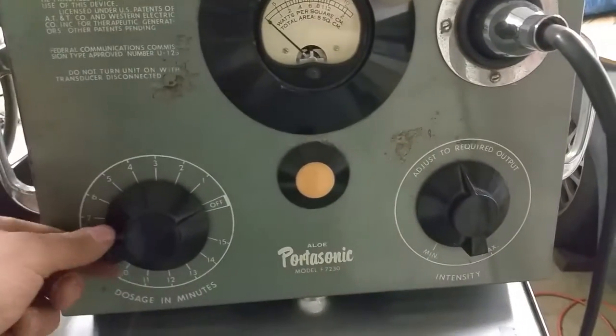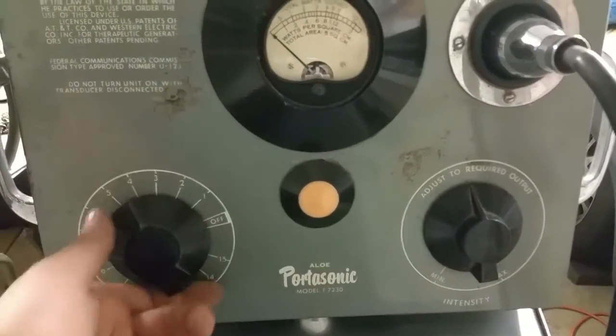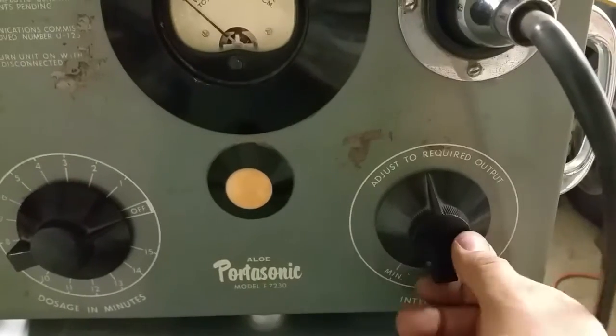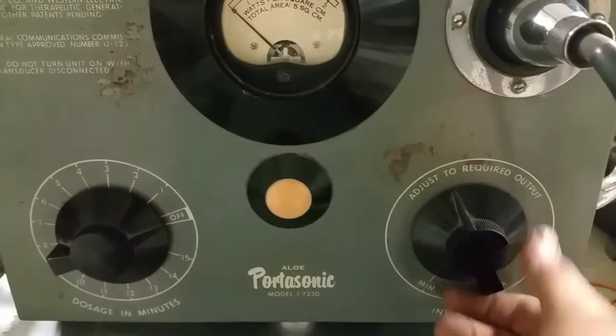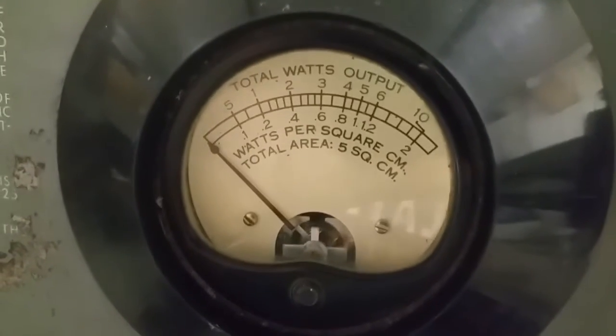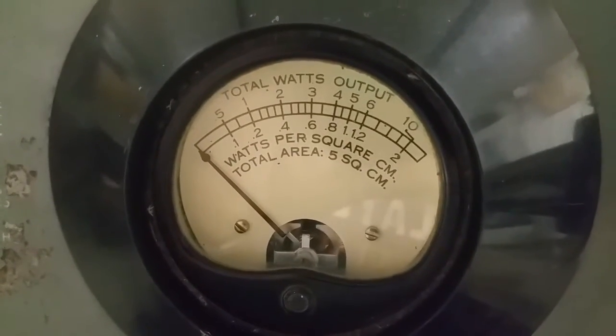So the front of it here you have dosage in minutes which you can set here which is a timer. You have the power light which always looks like it's on. It's very interesting. And then you have your required output. And the interesting thing is the gauge here is total watt output or watts per square centimeter.